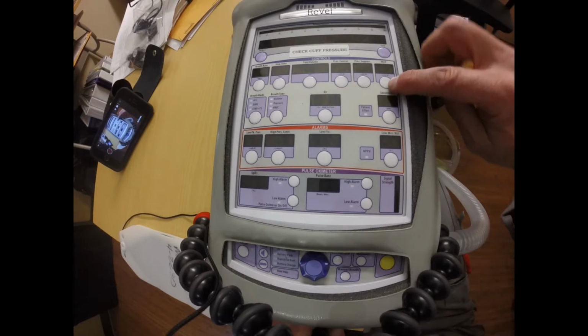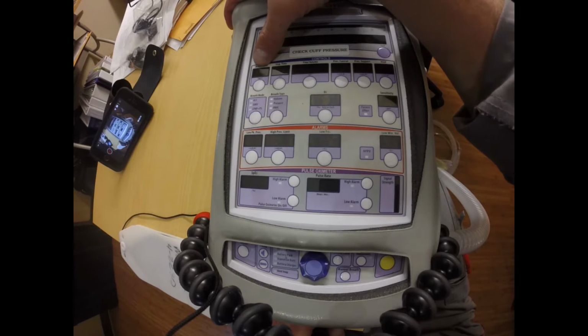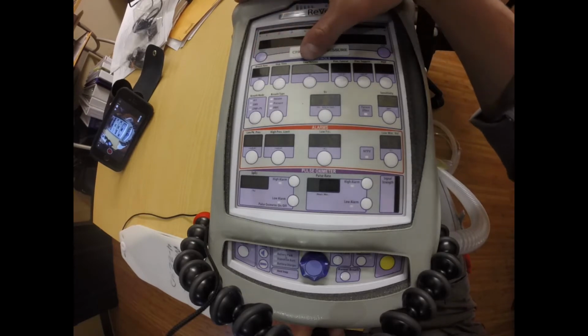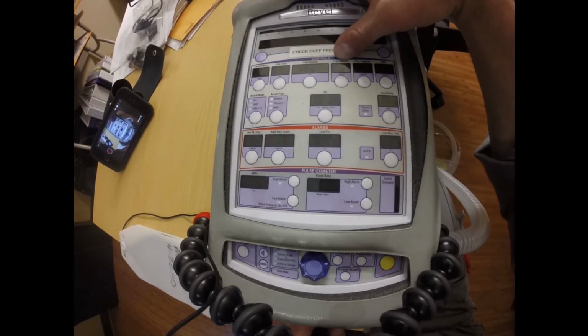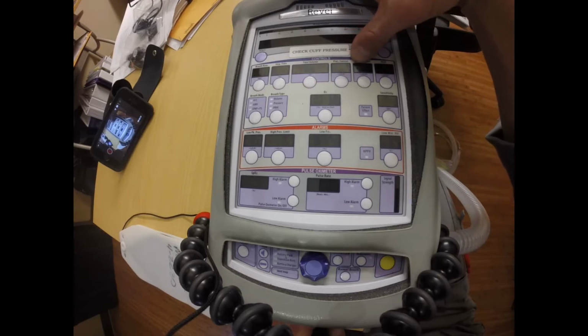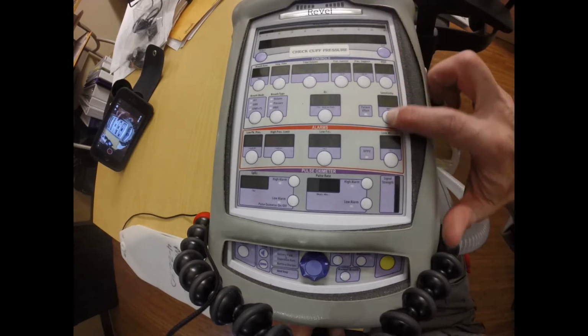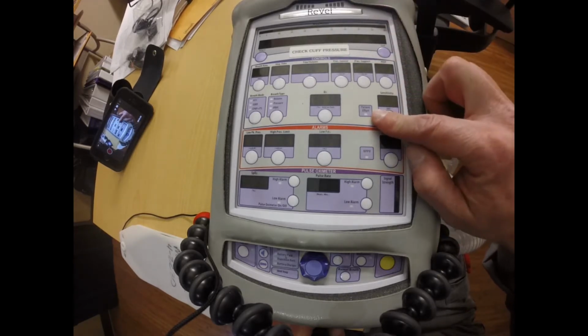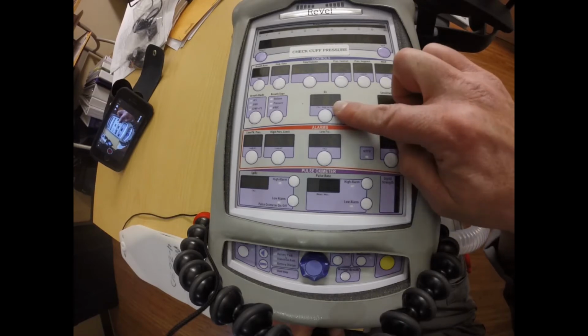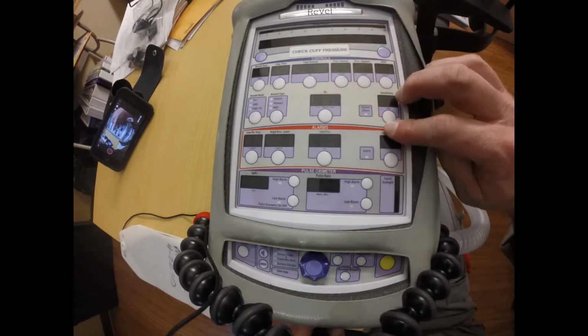The control panel is the area where we will set our breath rate, our inspiratory time, our tidal volume, pressure control if we choose to use that setting, pressure support, PEEP, sensitivity. You'll be able to see if the patient takes their own spontaneous effort here, what that light will illuminate. You'll be able to set your FiO2, your breath type, and your breath mode.